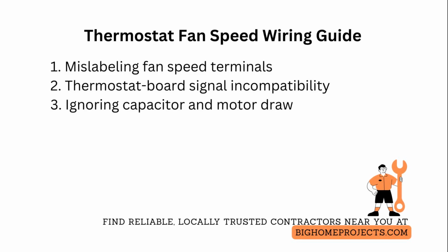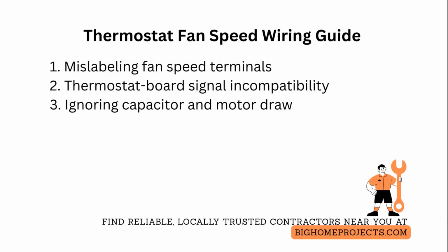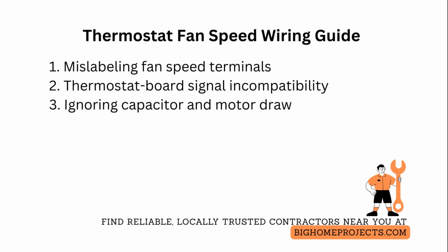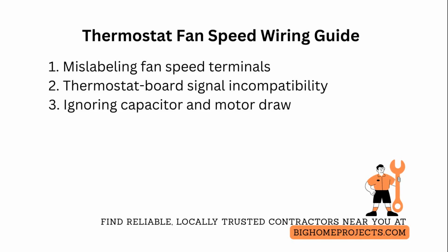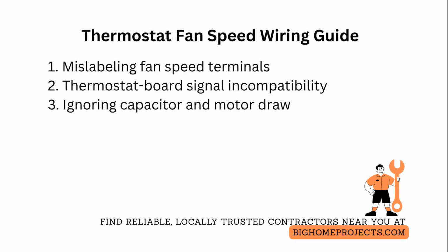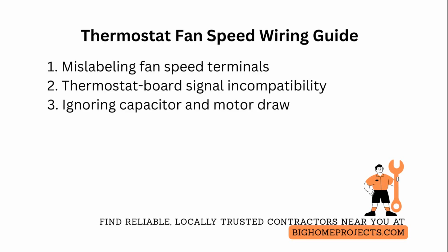Resolve this by fitting a compatible interface module or replacing the thermostat with one that offers on-off fan control or a board-compatible communicating interface. One of the usual problems is ignoring capacitor health and motor current draw when replacing boards, which results in slow or noisy fans at cooling speeds. Correct it by testing and replacing capacitors, measuring motor current against nameplate values, and installing proper overload protection or a relay pack if currents exceed board ratings.